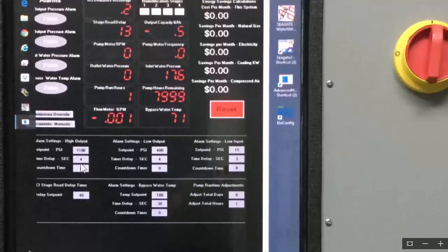This is adjustable. You push on this particular button here and it asks you for a password, and you can change this set point. With the time delay, the same thing. You push that button there, it asks you for a password, and you can put in a new value. And the same is true on the low output pressure side. Now this is where some testing gets involved also. You can actually set these up to put them into a normal operating value that you might have to test the actual alarms, and same with this one here and this one here. So besides actually having them do their function, you can set them up to test also.